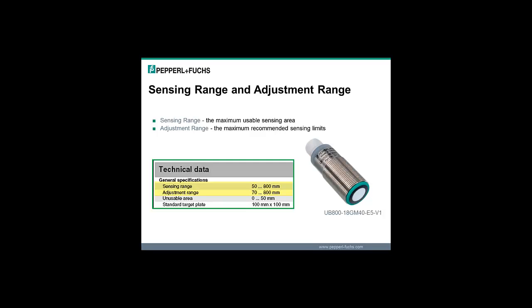And we do that because 50 is the near limit. If you get any closer than 50 millimeters to the transducer, you penetrate what is called the unusable area. And in that area, you can have some instabilities to your output. So we recommend that you get a little further away for your near distance so that you don't get into that area and have any stability issues. And we'll talk about the unusable area next.